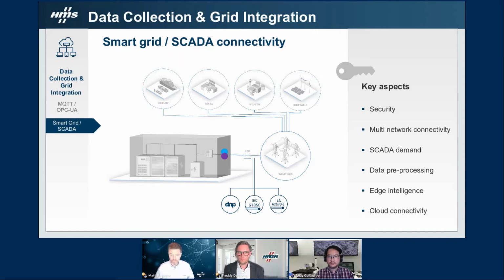Data pre-processing: for example, Modbus protocol doesn't support decimal points, so values need to be scaled before they are sent. Also, Modbus doesn't support timestamping, which may be required by the SCADA system.